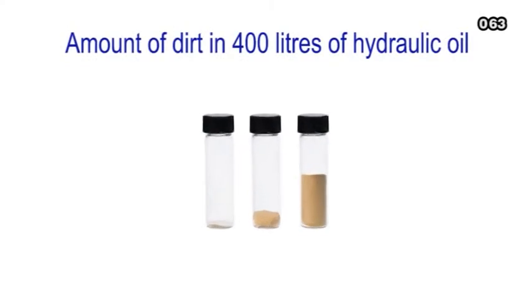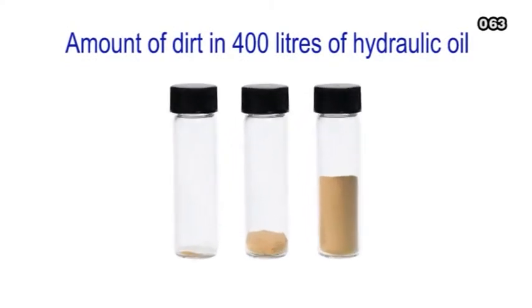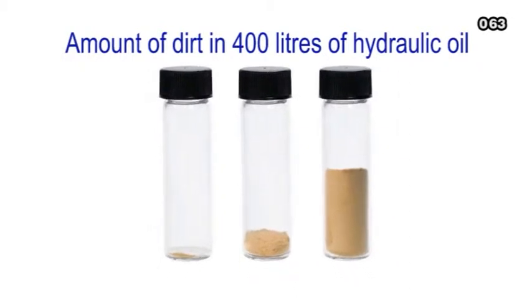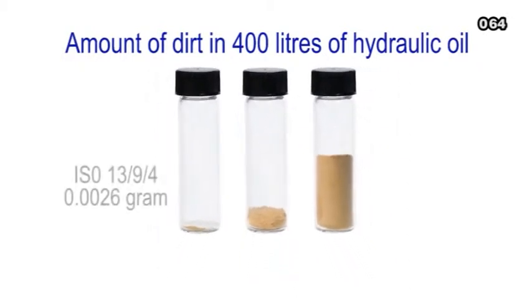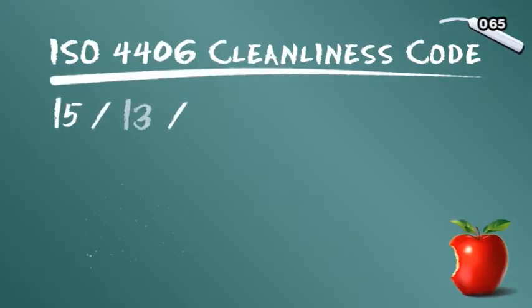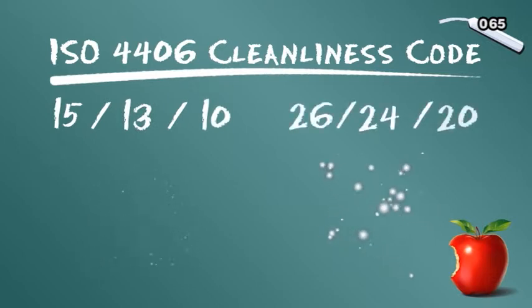Looked at another way, the dirt in these three glass containers each represents a different ISO 4406 cleanliness level. From a tiny fraction of a gram on the left, to about a third of a gram in the middle, to almost 5 grams of dirt on the right. Note how the three cleanliness code numbers also get progressively higher to indicate more dirt and less oil purity.